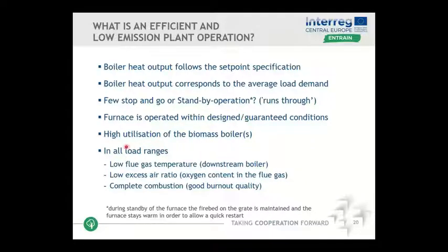In all load ranges, this is very important, not only during official emission measurements from our authorities. No, in all load ranges, we want to have low flue gas temperatures and low emissions and high efficiency, meaning low excess air ratio, for example. So this is the main idea of what we want to achieve.